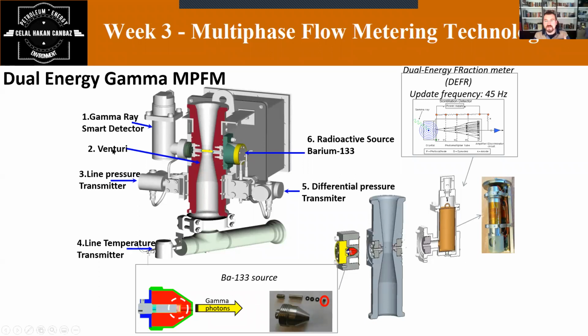This is what we call mass attenuation. It collides, loses some part of its energy and reflects to the plate, and you make the measurement. You are getting the measurement of this mass attenuation: how much energy it loses, and what molecule it collided with. It says it collided with an oil molecule, or that this was a water molecule, and it's doing this 45 times a second.